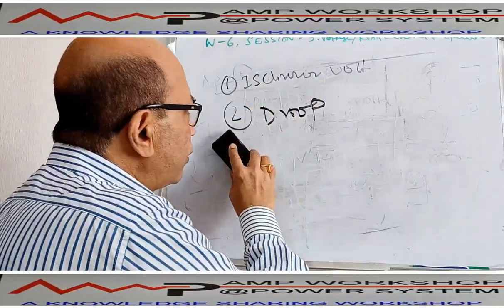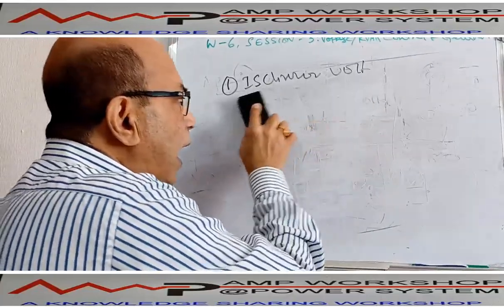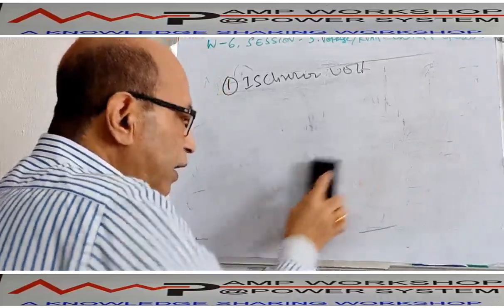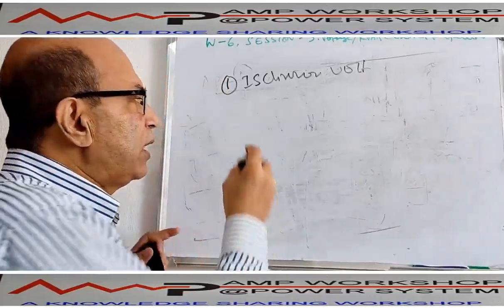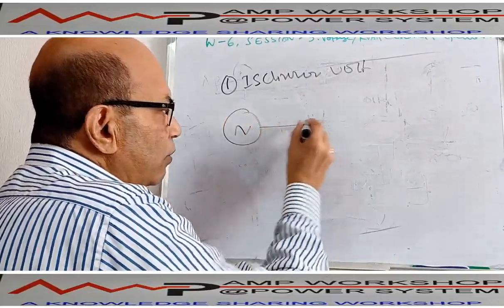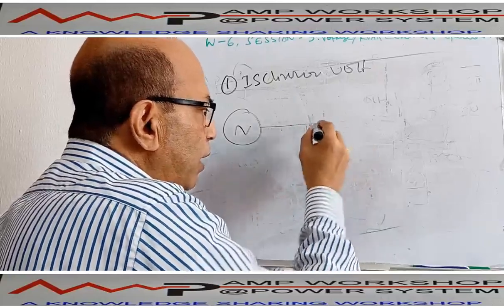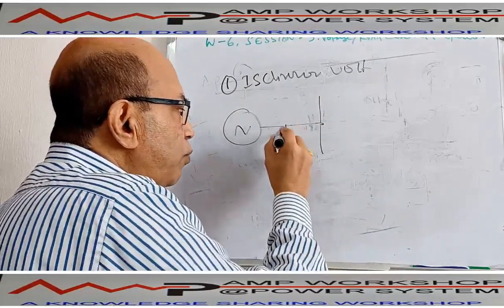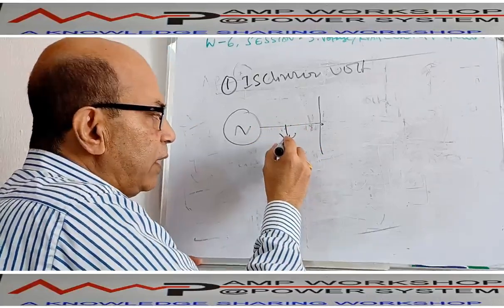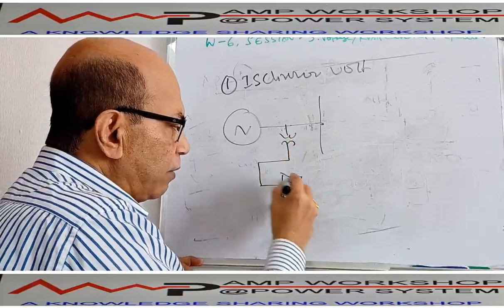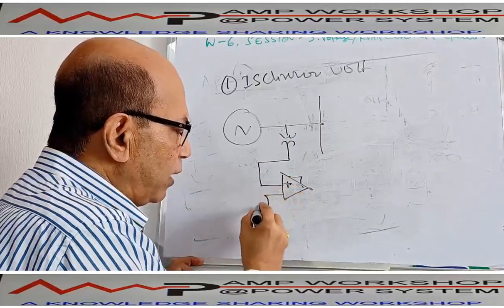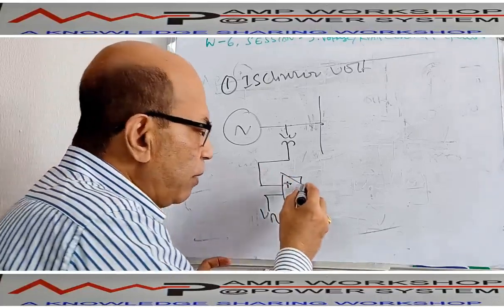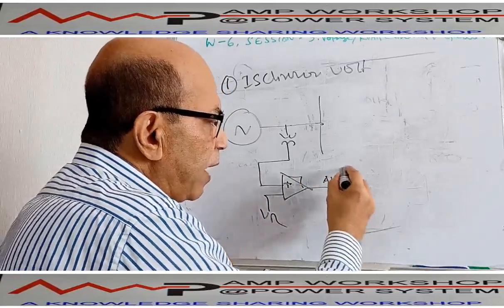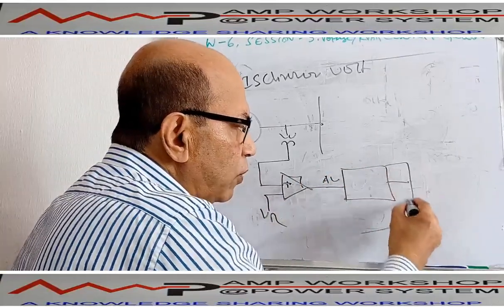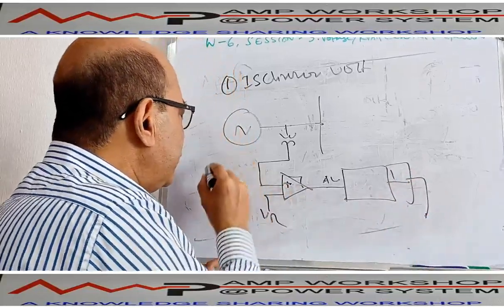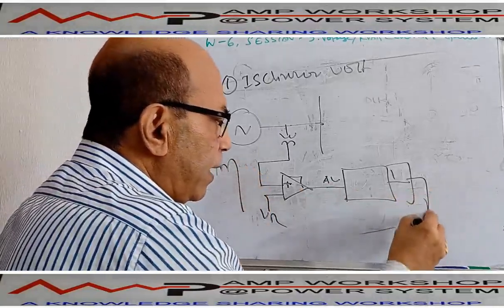Normally, isochronous mode we use for a single machine. In a single machine system, we use the isochronous mode. Suppose a single generator is running and we want to run it in isochronous mode. This generator is running, giving power to the bus. So we put a PT, or if it is low voltage, we directly tap the voltage and give it to the controller. This is our controller. This is the negative supply and the positive V reference is already there, as we discussed before. Immediately it will compare and get the delta V. Delta V will go to the controller and the power circuit, and it will give the output. The output comes as DC. That DC will come to the generator exciter rotor field. It will come directly from here to the rotor field.